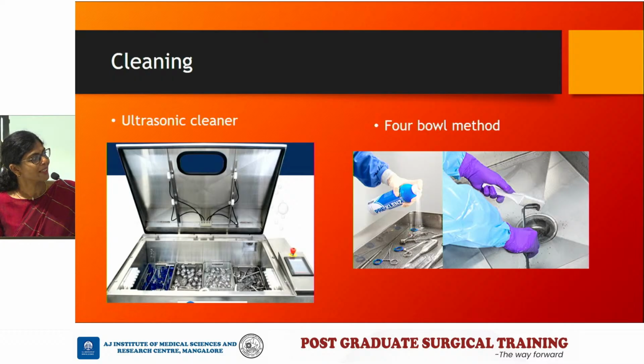Now, coming to the instrument cleaning, the first thing is cleaning before going in for sterilization. Cleaning is usually done with the help of an ultrasonic cleaner, in which an enzymatic removal agent is applied, or an equally effective method which is used in most OTs is the 4-bowl method, where 4 bowls are taken with distilled water, and in the first bowl, a cleaning agent is applied and your instruments are soaked to remove the blood and other debris.